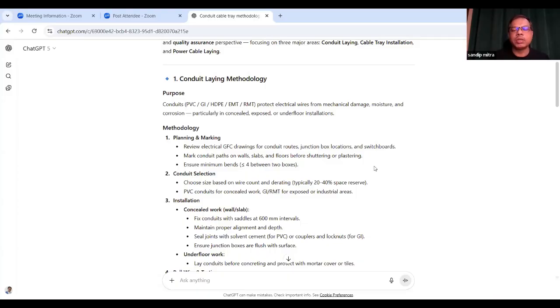It may be open conduit or concealed conduit. It depends on the requirement of the project. It may be through concrete, it may be through brick wall, it depends. So based on the project specification, you have to prepare the methodologies. Ensure minimum bends, maybe less than 4 between two boxes. These are the things mentioned in the specification, or suppose you need to follow the NBC guideline.